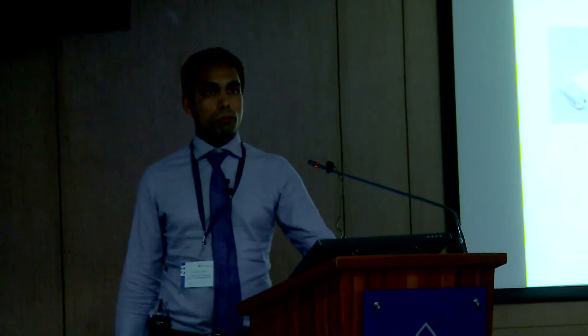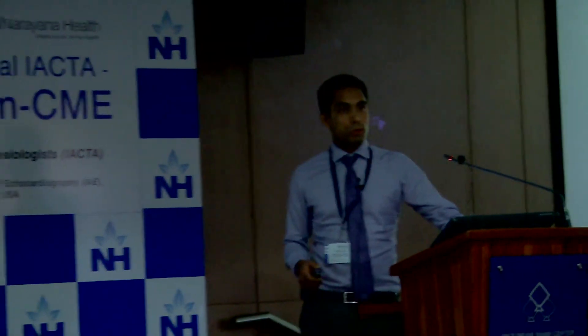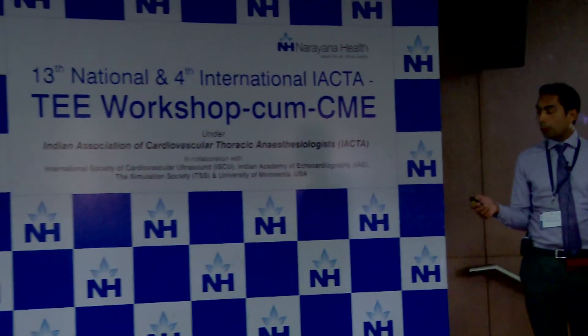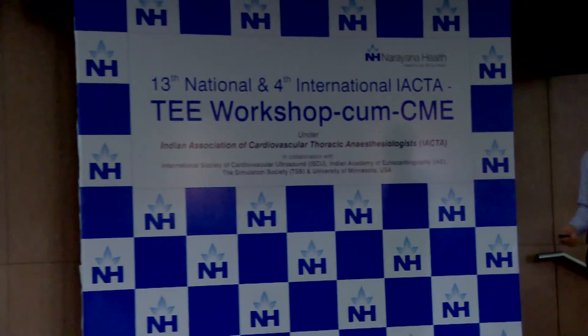The third one is called a micro-convex probe. It is similar to a curvilinear probe but has got higher resolution. So it has the best of both, and it has the added advantage that it can be placed nicely in between the ribs, so you can get a better view.